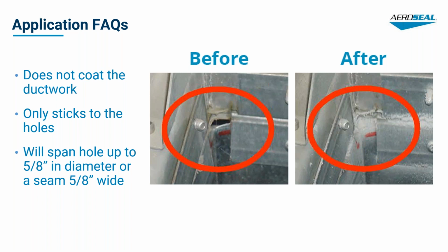In fact, we've found that most multi-floor buildings can be treated with Aeroseal without disruption to occupants. Our project technicians will block off the building's diffusers, grills, and registers and isolate the air handling unit, then connect the Aeroseal equipment and perform a pre-seal test, which sets the leakage benchmark.